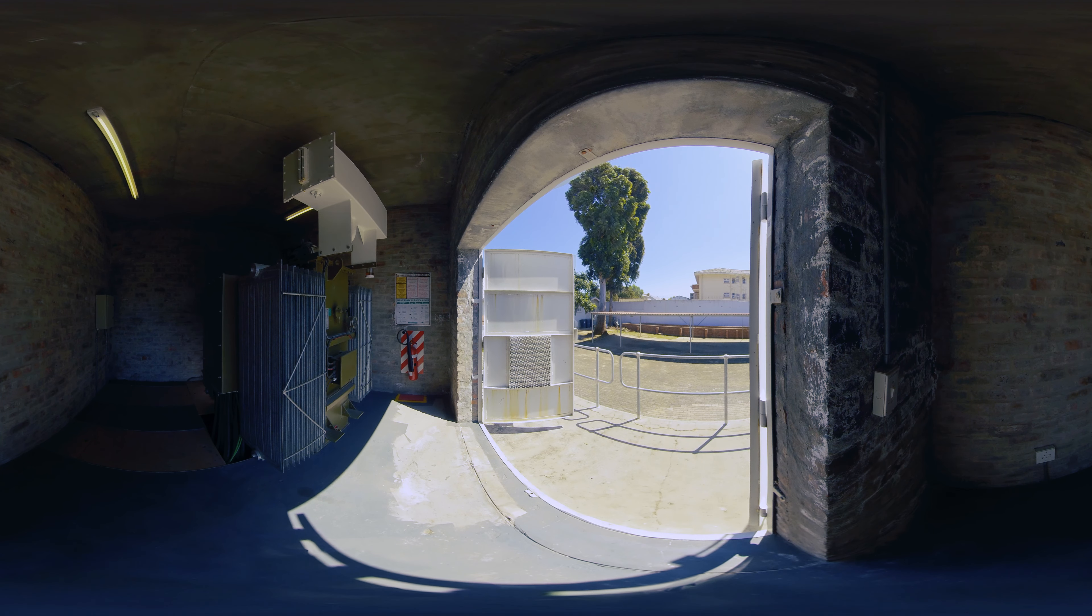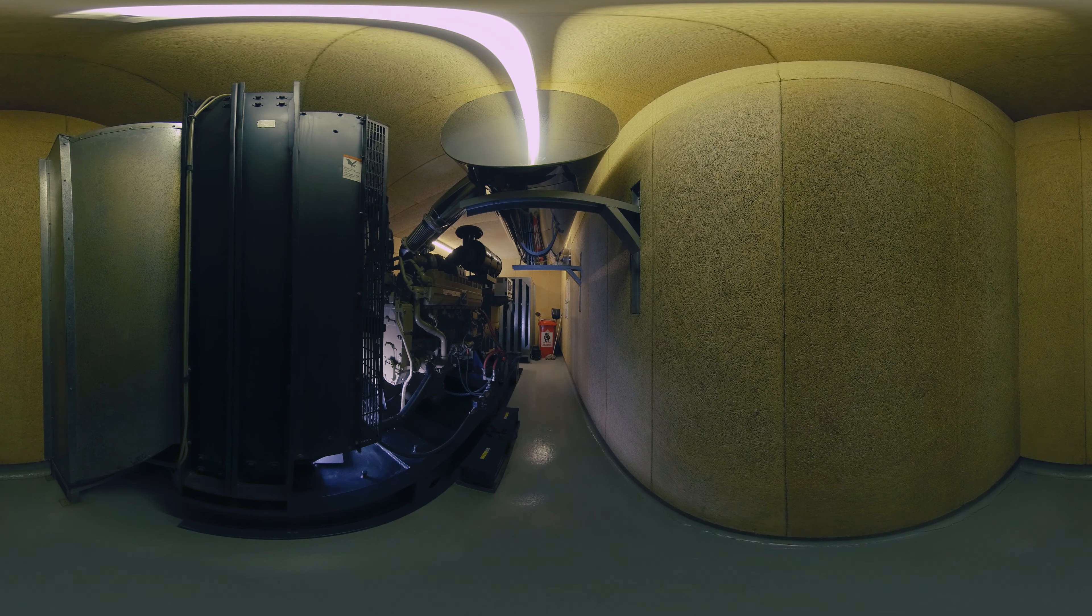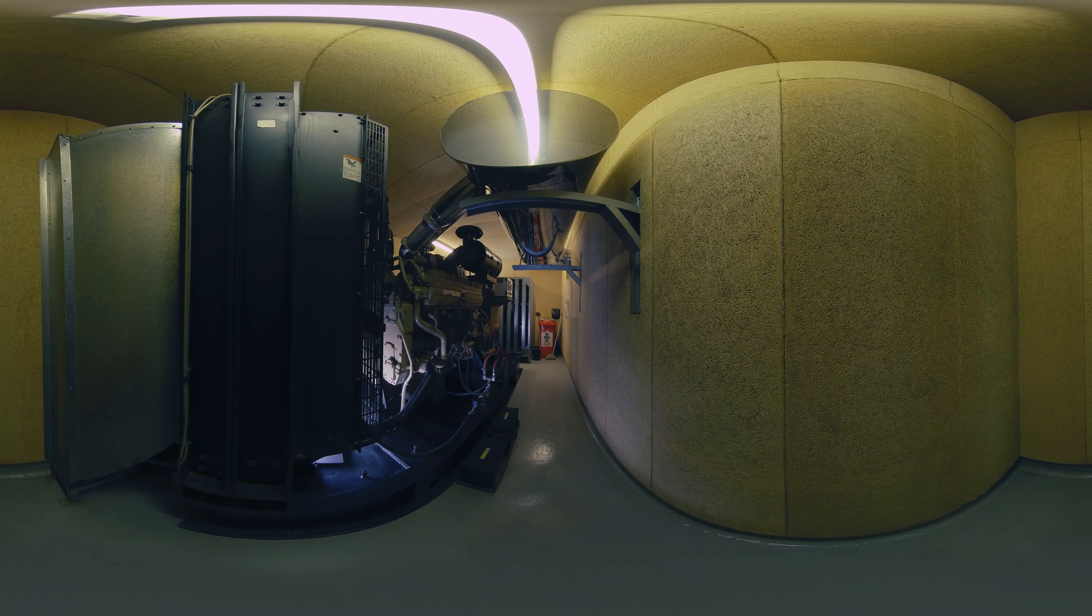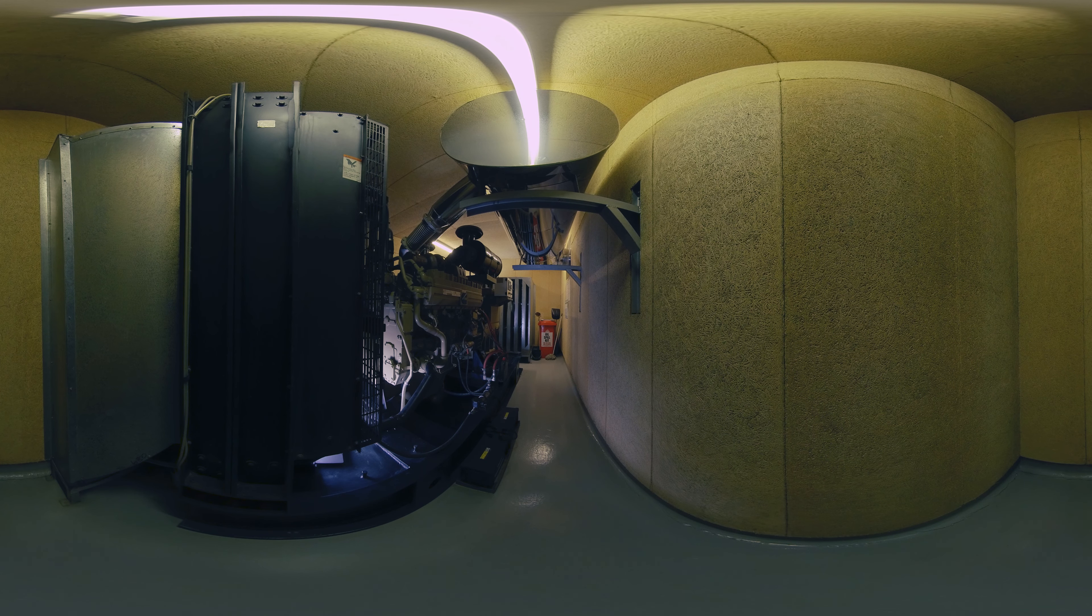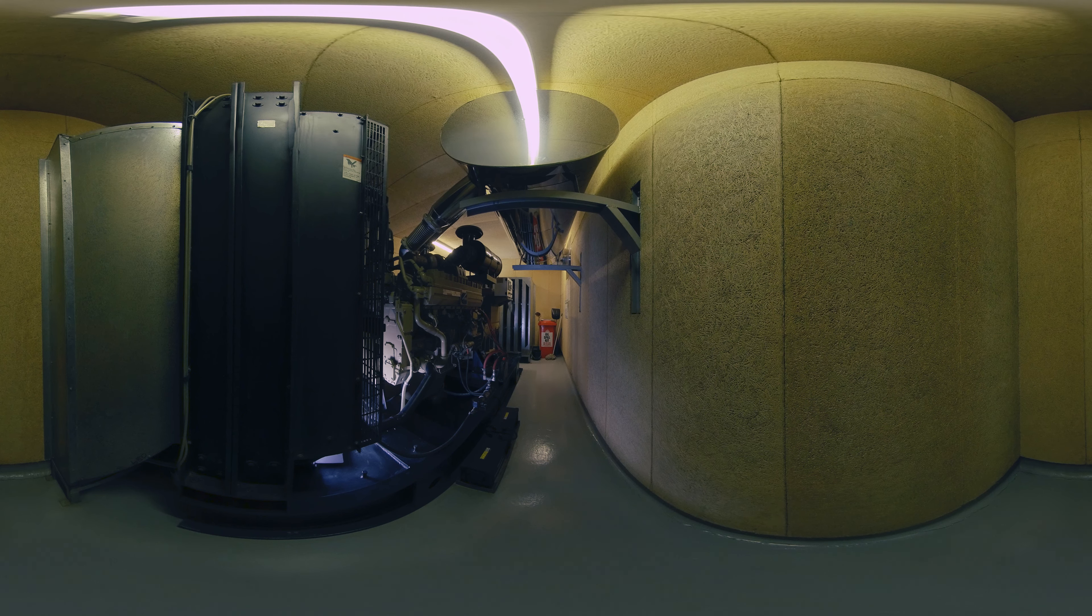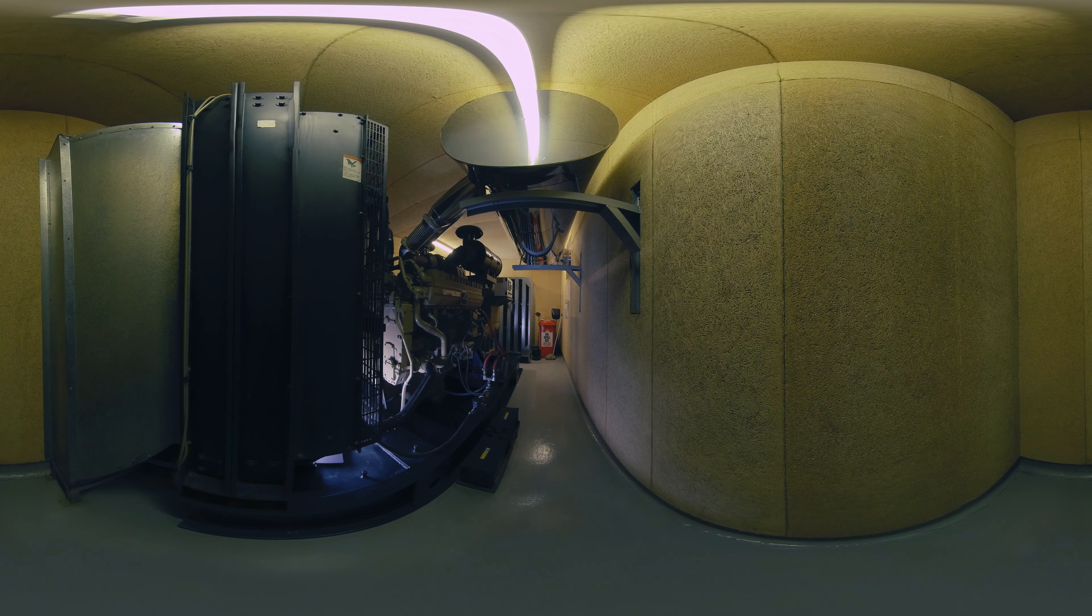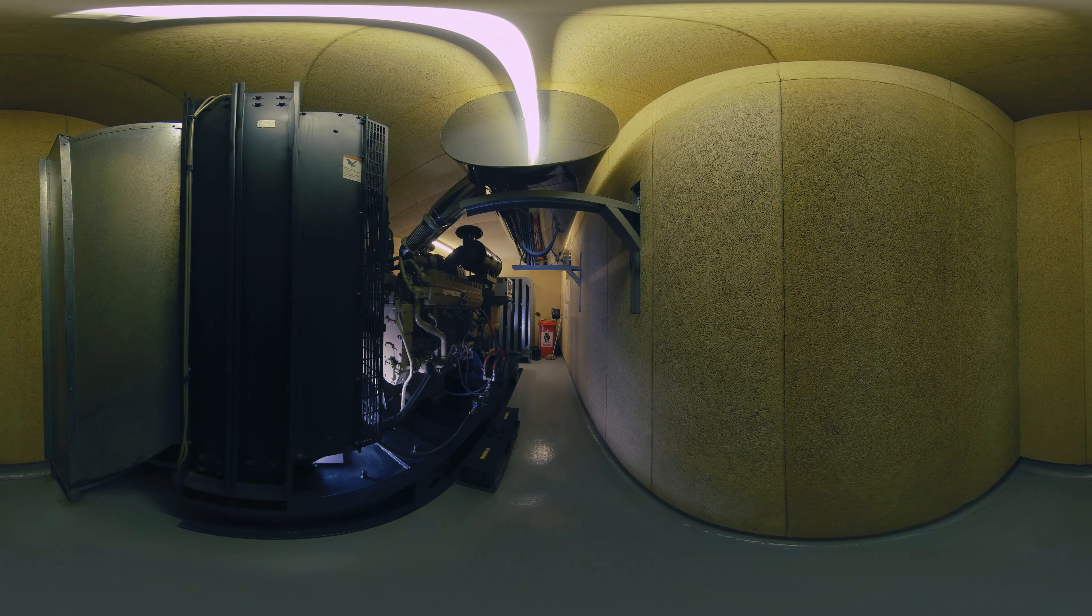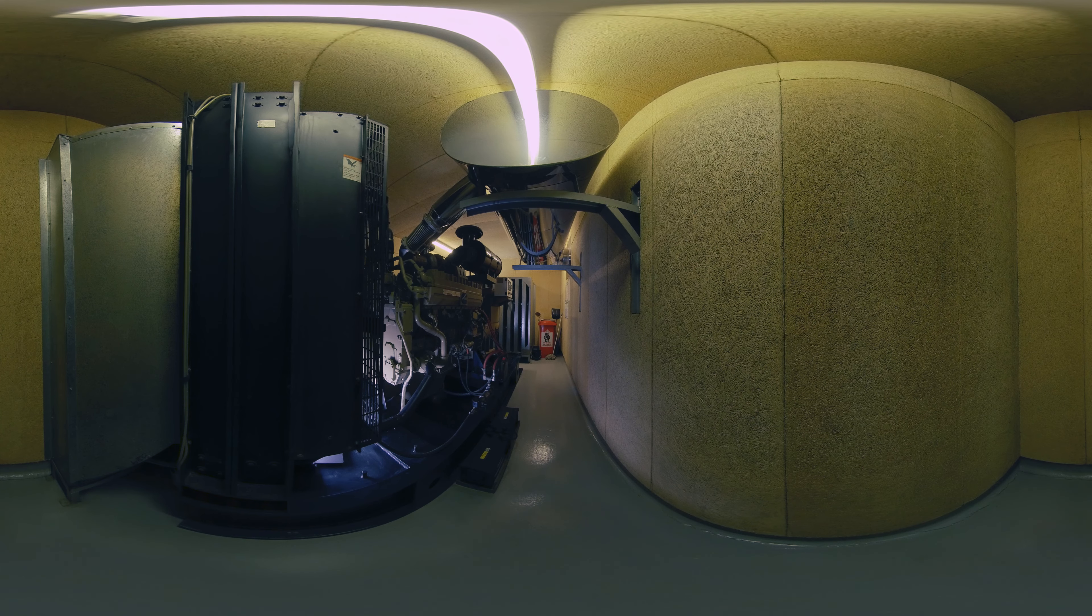In the case of a power cut, this 1,030 kilovolt-amp generator kicks in and can run for up to eight hours, during which it uses 1,200 liters of diesel.